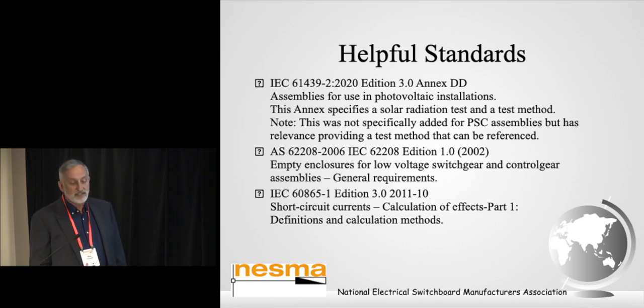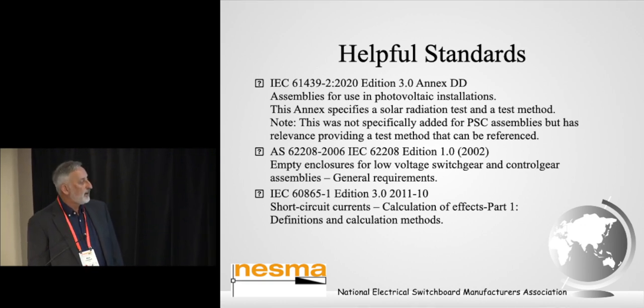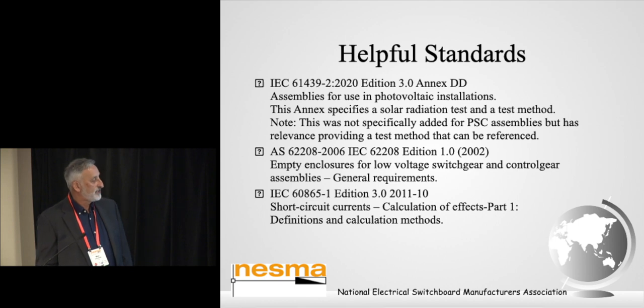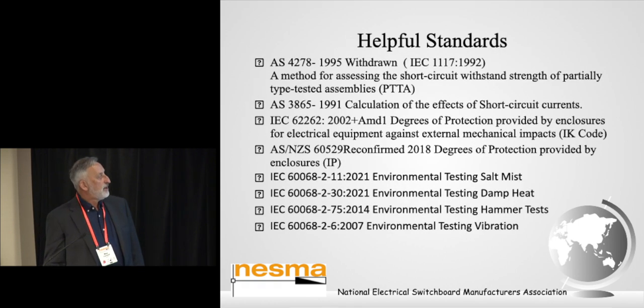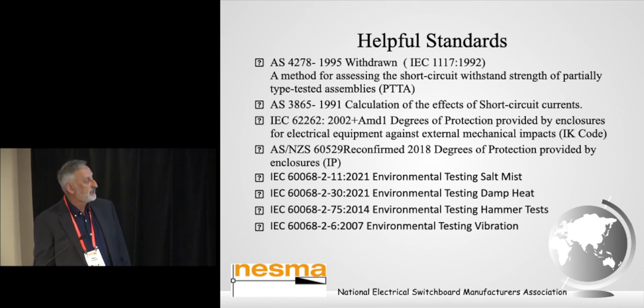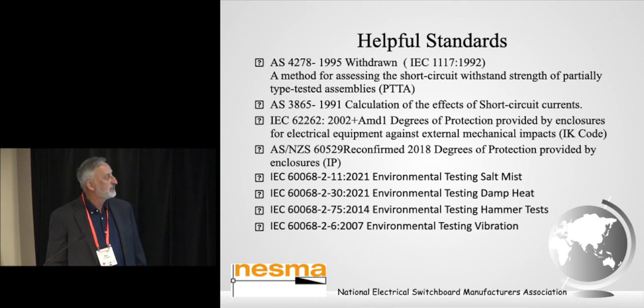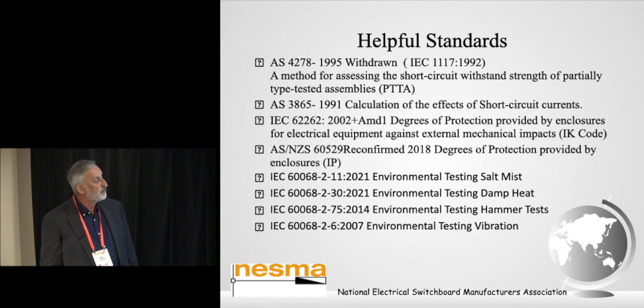62208, which is the empty enclosures, so where you can test an empty enclosure for suitability, and it is cross-referenced in the 61439 series. 60865, edition 1, Part 1, edition 3, gives you short circuit currents, calculation of effects, and definitions and calculation methods. Australian Standard 4278, 1995, is a withdrawn standard, a method for assessing short circuit withstand strength of partially type tested assemblies. Australian standards have a methodology, once the standard's over 10 years old, they want to withdraw it unless the committee is active and wants to reconfirm the standard. So there are a lot of standards that can be pulled and withdrawn, even though they might still be wanted by the relevant industries.